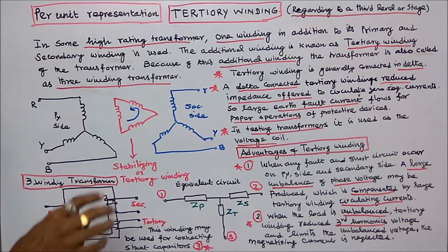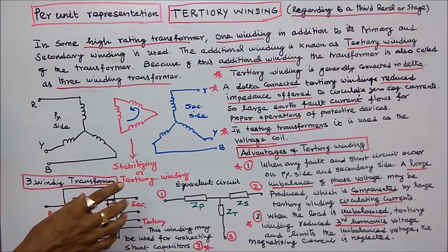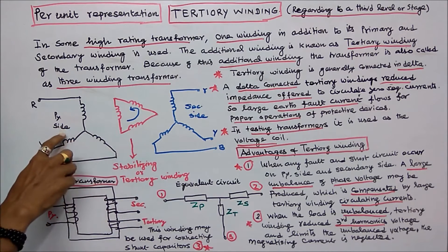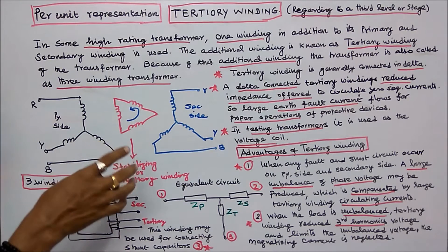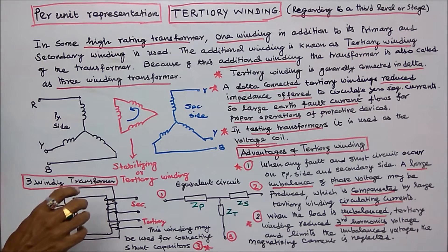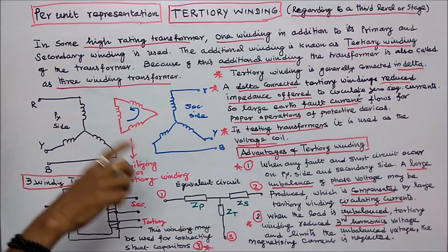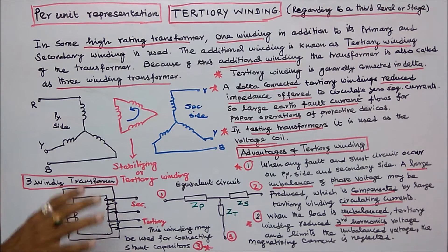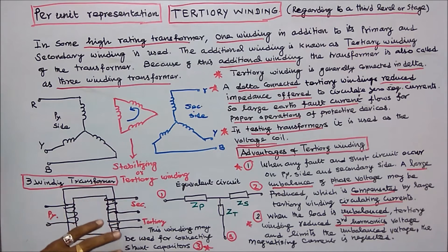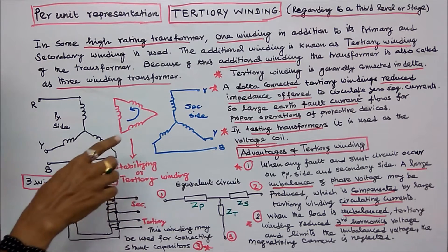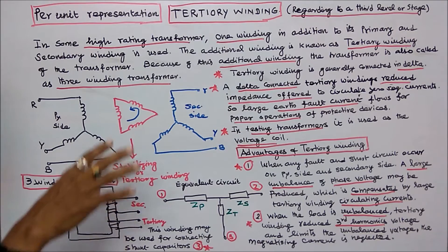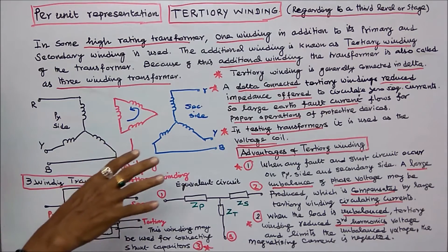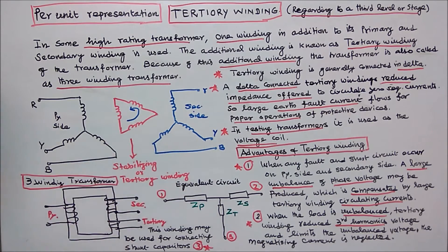Advantages of tertiary winding: Number one — when any fault and short circuit occur on the primary side and secondary side, a large unbalance of phase voltage may be produced, which is compensated by large tertiary winding circulating currents. Number two — when the load is unbalanced, the tertiary winding reduces third harmonic voltage and limits the unbalanced voltage. The magnetizing current is neglected. Number three — the winding may be used for connecting shunt capacitors.